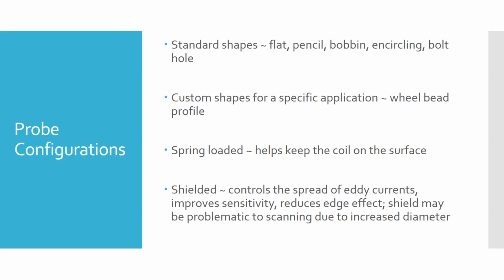Other configurations, looking at the inside, we can have more than one or multiple coils. We can also have things like shielding and loading, where we put different materials around the outside of the probe to limit interaction with things around it, or load the coil with materials - typically ferrous - in the center of the windings, to concentrate magnetic fields directly under the probe, especially if we're trying to get a deeper depth of penetration.